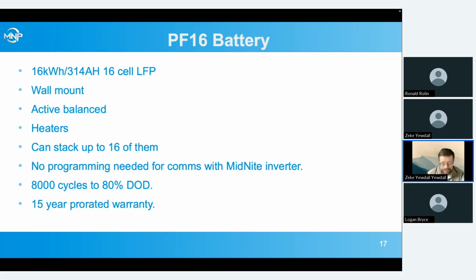Moving on from the inverter to our battery, we've got the PF16 wall mount battery. This one's actively balanced and has built-in heaters. So those are kind of the two big differences, other than just being a larger size than our other battery. All of our batteries, there's no programming needed for the communications other than setting the inverter to MidNite battery and plugging the cables into the right spots. There's no dip switches to set or addresses or anything. You can have up to 16 batteries on one inverter bank.